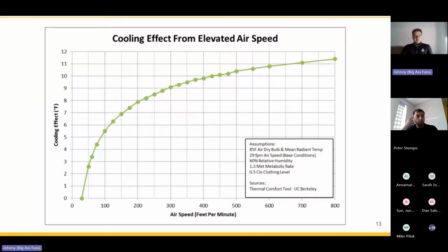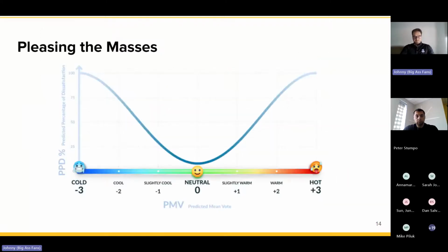So you don't want to disrupt the space, but you want to add a bit of supplemental cooling and airflow to create the comfort we need. At 120 feet per minute on this chart, we're talking about 6, maybe up to 7 degrees of perceived cooling effect, which is pronounced. So you can really beef up your cooling system by just adding some airflow to a given environment. That's what we're doing.